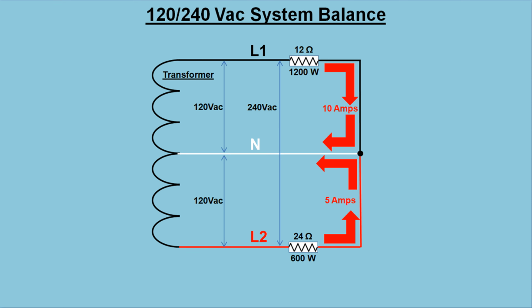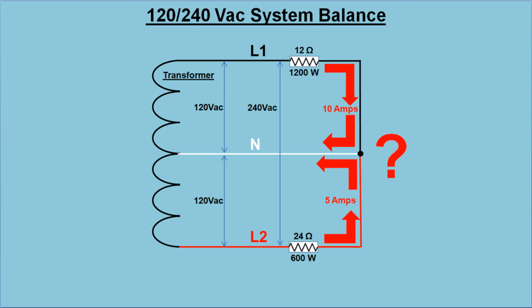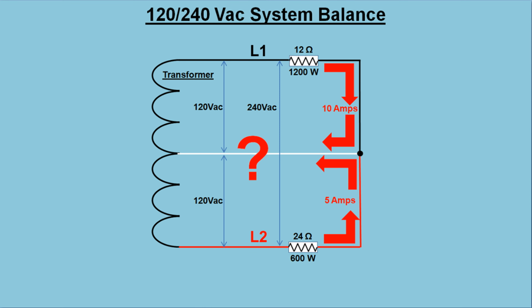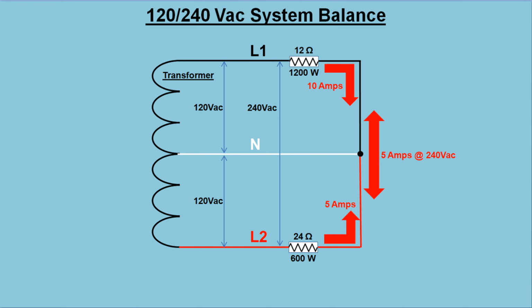If we put both loads on at the same time, we get current flow on both lines to neutral. But where does all that current actually flow? Does the neutral see 15 amps as it appears to here? What's really happening? The unequal current on line 1 and line 2 is called an imbalance. What's really happening is that the two 120 volt loads create a 240 volt load with 5 amps flowing between line 1 and line 2. The remaining 5 amps of unbalanced current on line 1 flows on the neutral at 120 volts AC.